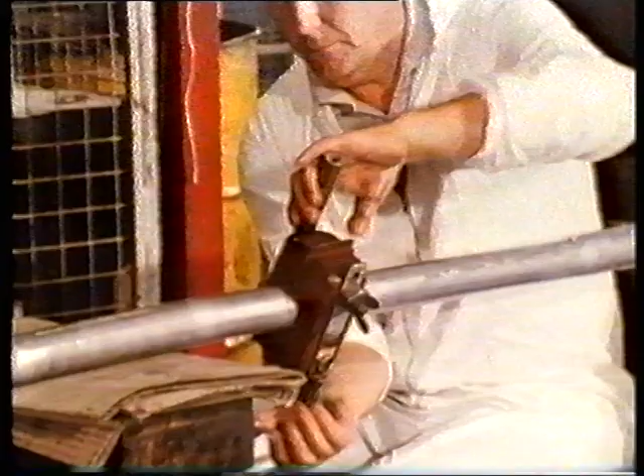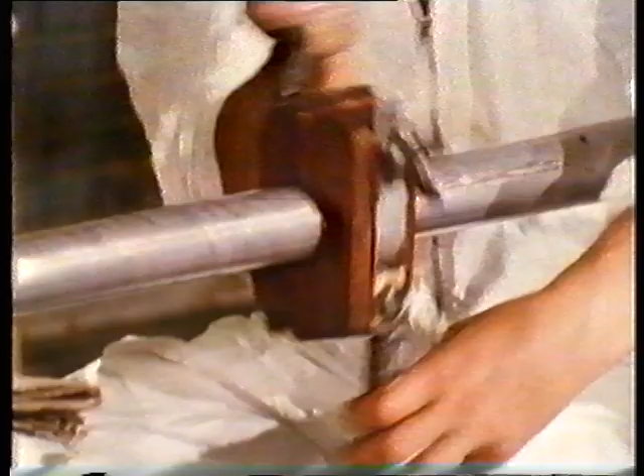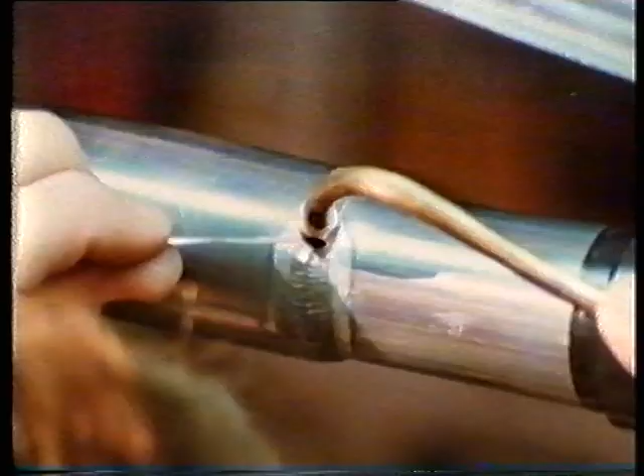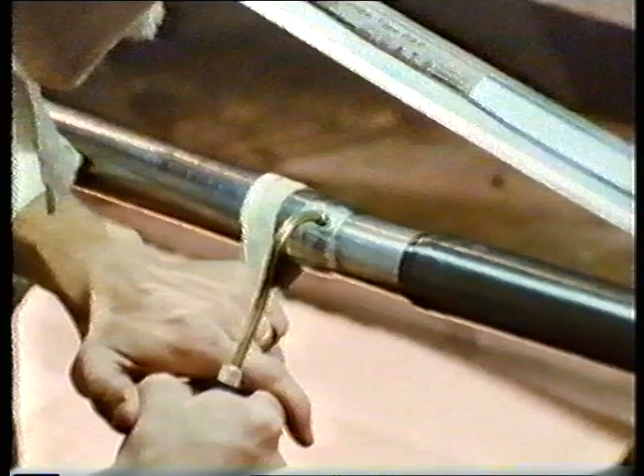Then, in order to produce a tight fit and to ensure there is no increase in diameter, the lead sleeve is swaged down onto the cable. Now comes a vital process, burning lead into the sleeve to seal it against any possibility of moisture seeping into the cable. This is very skilled and painstaking work.